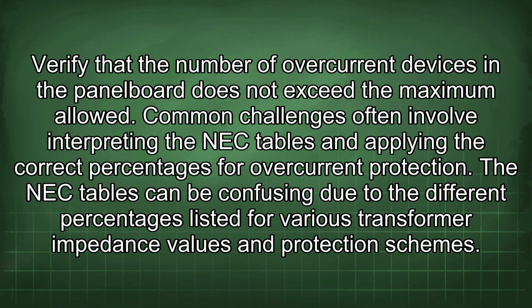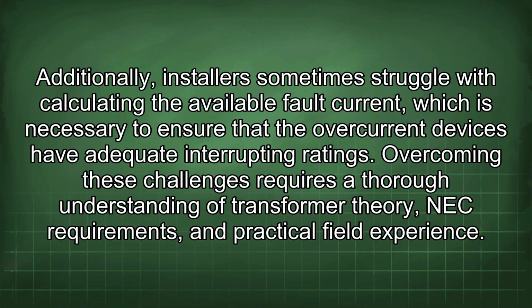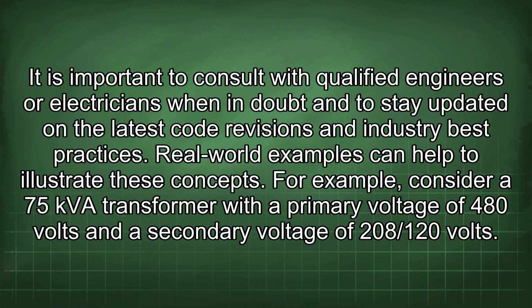Common challenges often involve interpreting the NEC tables and applying the correct percentages for overcurrent protection. The NEC tables can be confusing due to the different percentages listed for various transformer impedance values and protection schemes. Additionally, installers sometimes struggle with calculating the available fault current, which is necessary to ensure that the overcurrent devices have adequate interrupting ratings. Overcoming these challenges requires a thorough understanding of transformer theory, NEC requirements, and practical field experience. It is important to consult with qualified engineers or electricians when in doubt and to stay updated on the latest code revisions and industry best practices. Real-world examples can help to illustrate these concepts.